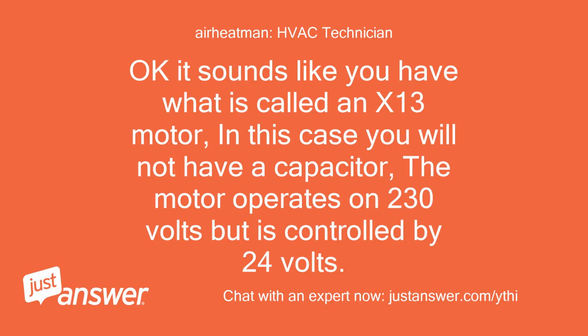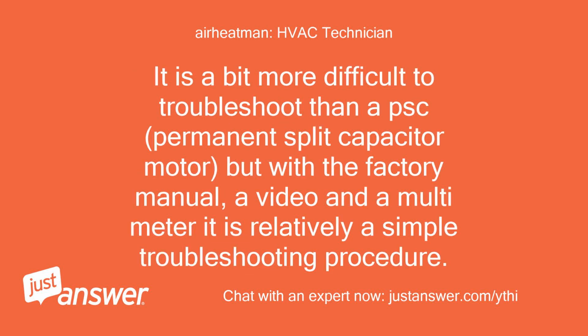Okay, it sounds like you have what is called an X13 motor. In this case you will not have a capacitor. The motor operates on 230 volts but is controlled by 24 volts. It is a bit more difficult to troubleshoot than a PSC, permanent split capacitor, motor, but with the factory manual, a video, and a multimeter, it is relatively a simple troubleshooting procedure.